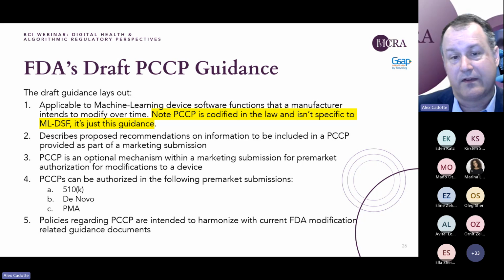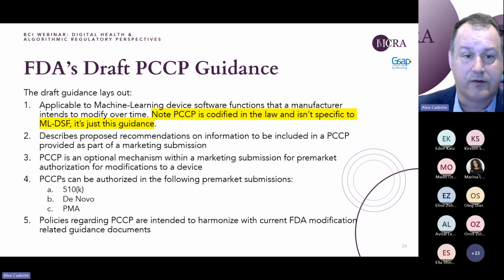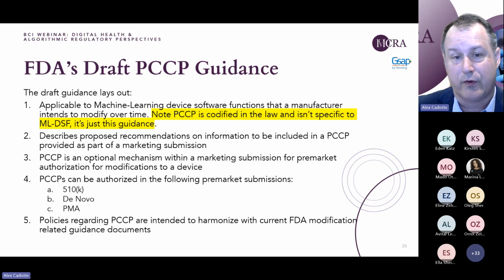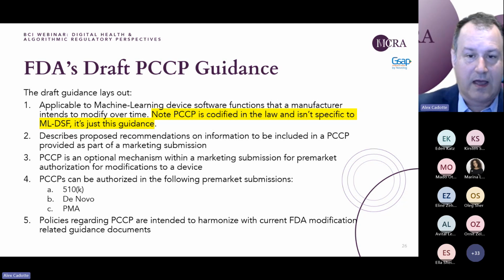Also, the PCCP is a concept that's intended to harmonize with existing guidances that are out there about changes. To be clear, if those guidances already say that this is a function that you don't need to come in to FDA for, you don't need to include those functionalities in a PCCP in order to do those things. So those guidances still apply, and the PCCP is typically expected to be a special carve out for something that you normally wouldn't expect to be able to make without coming in to FDA with an additional submission. So essentially, this is a very specific carve out in this space, allowing you to make modifications to your device that you've pre-specified, and FDA has authorized that you are not only allowed to make those specific changes, but you have the proper quality system and procedural machinery in place to carry out those changes.